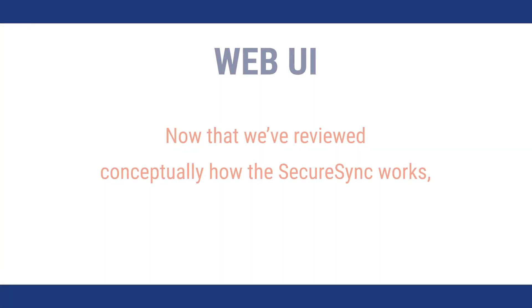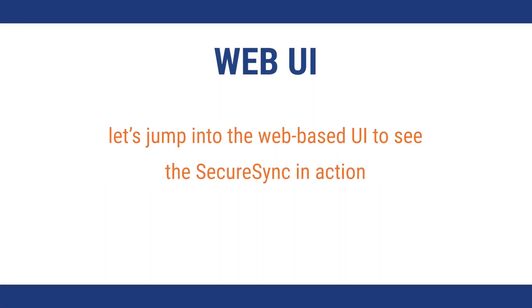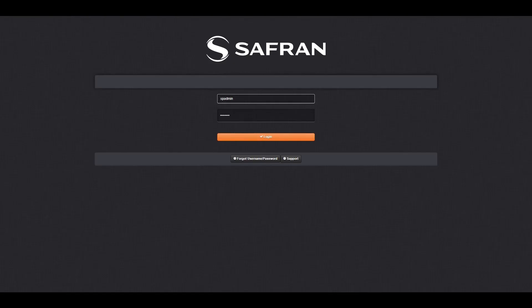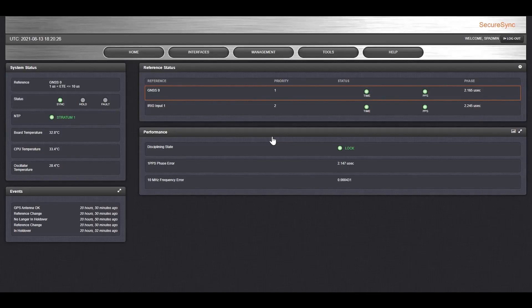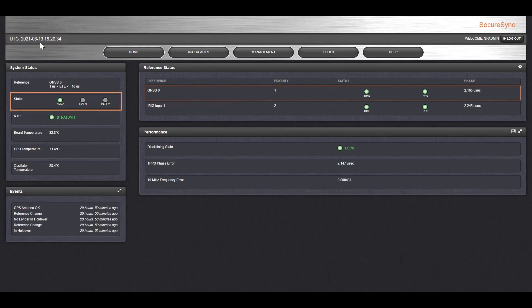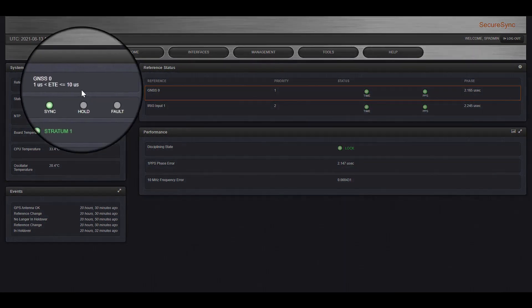Now that we've reviewed conceptually how the SecureSync works, let's jump into the web-based UI to see the SecureSync in action. SecureSync provides you with a web-based interface to monitor activity. The first thing you'll do is log in with a username. And I'll describe what's shown here. First, you'll see the current time of the unit. In the main screen, you'll see the status of the system. The reference I'm using right now to synchronize is GNSS, GNSS zero, and the approximate error that I'm seeing is between one microsecond and 10 microseconds.